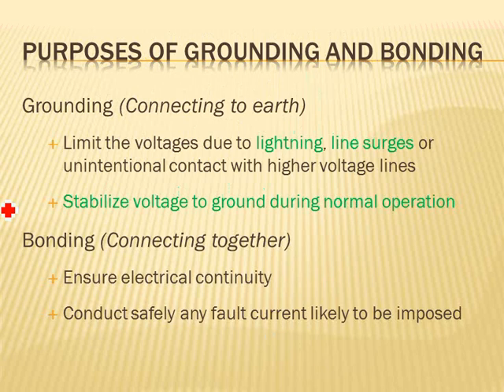Now we'll talk about the advantages of these systems. So, bonding. The bonding ensures electrical continuity and conducts safely any fault current likely to be imposed. The last thing you want is a metallic tank with a pump in it, where the frame of the pump is isolated from the tank, and the tank gets energized by one of the hots because of a malfunction, and you go grab one side of that tank, and you are barefoot.